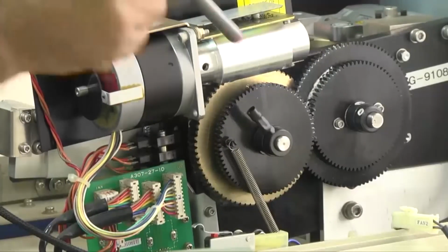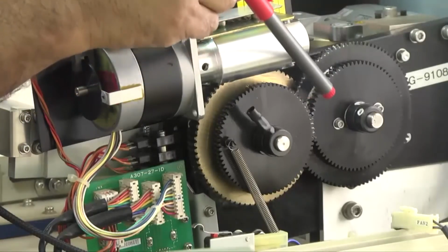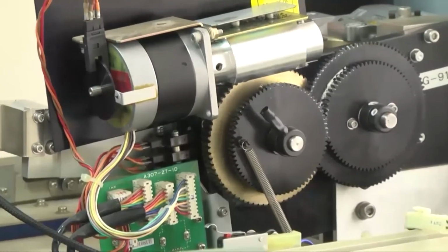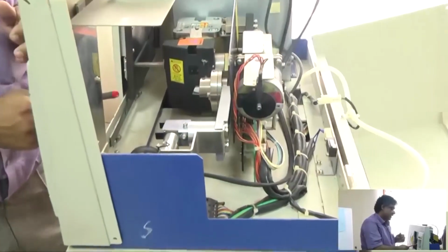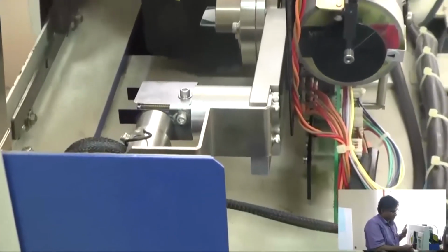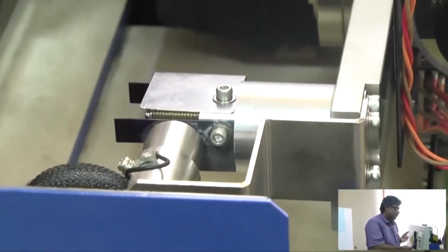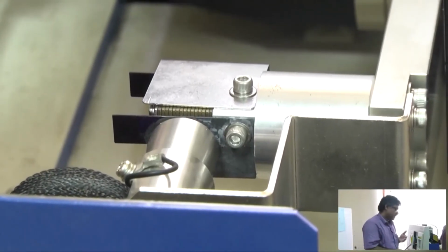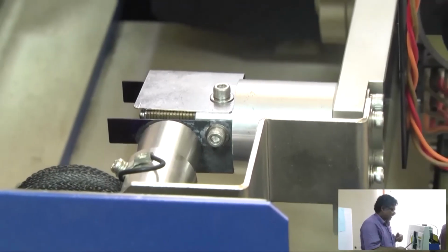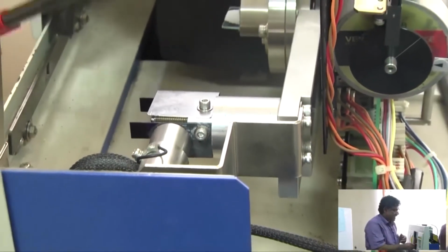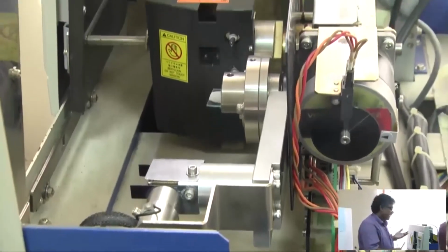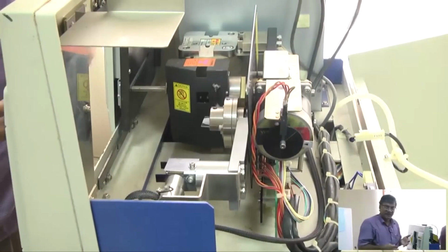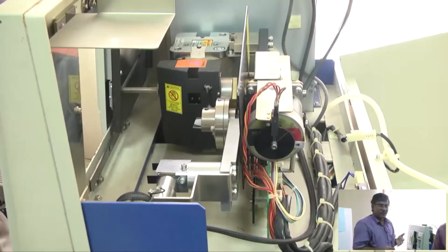That stepper motor is also standard, and is connected with this detector holder. From computer programming one can choose the step of the change of the angle 2 theta, or the angle of the detector, and we scan from 0 to 90 degree. On screen we will get the X-ray diffraction pattern. Now that X-ray diffraction pattern we have to analyze for getting the information.